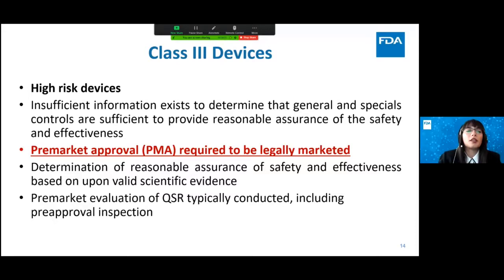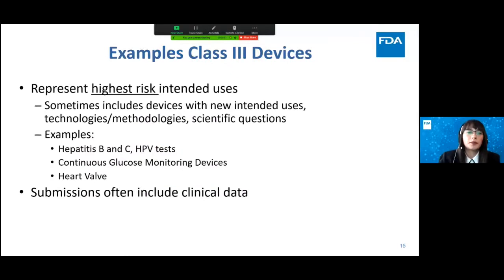In addition to that, there are requirements in the pre-market evaluation for quality system requirements, and FDA may do a pre-market inspection for these types of devices, but they definitely review that information during the evaluation. Some of the examples are tests for hepatitis B and C, HPV tests, continuous glucose monitoring devices, heart valves. As you can imagine, if they fail, it's really catastrophic and can cause some serious injury or adverse events to patients. And most often in this category, we do see clinical data presented.